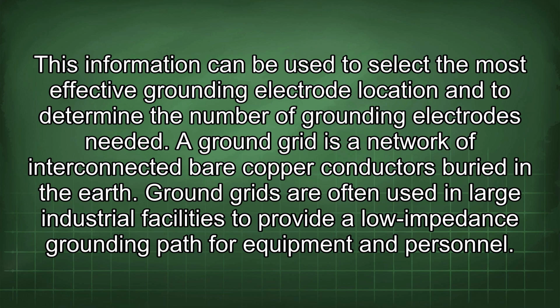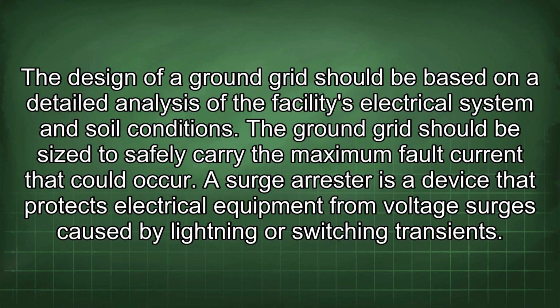A ground grid is a network of interconnected bare copper conductors buried in the earth. Ground grids are often used in large industrial facilities to provide a low-impedance grounding path for equipment and personnel. The design of a ground grid should be based on a detailed analysis of the facility's electrical system and soil conditions. The ground grid should be sized to safely carry the maximum fault current that could occur.